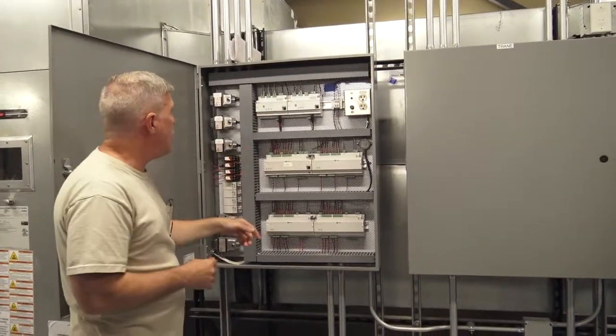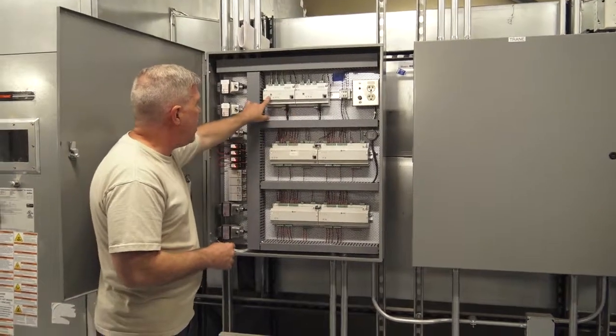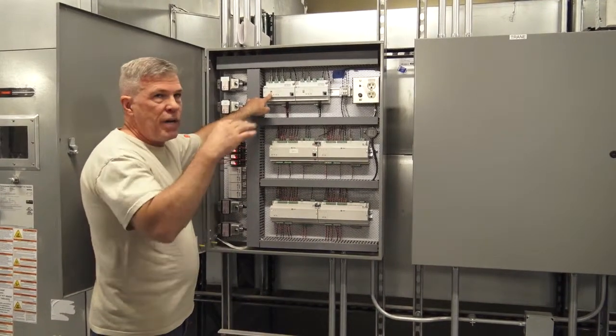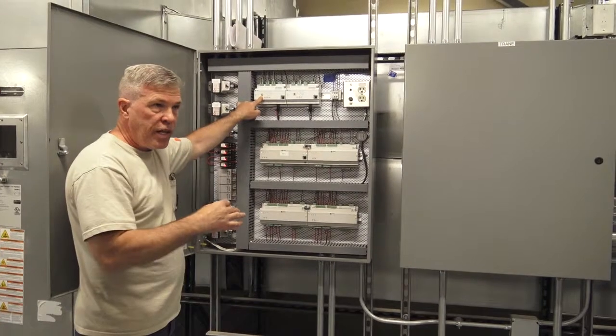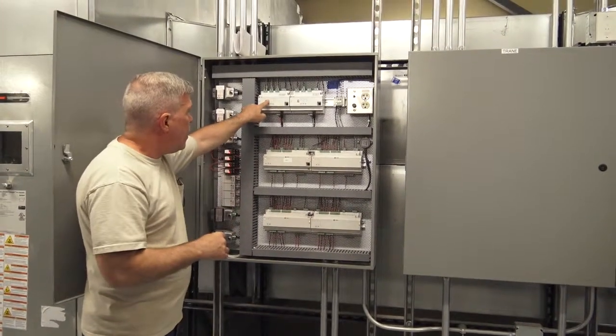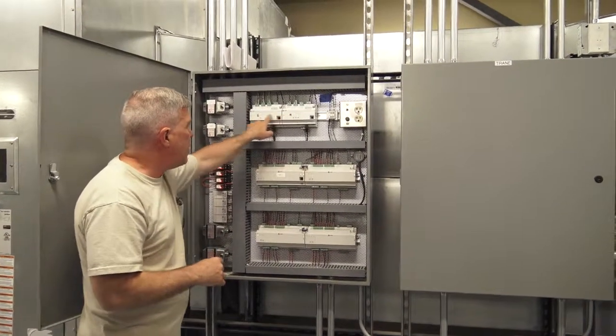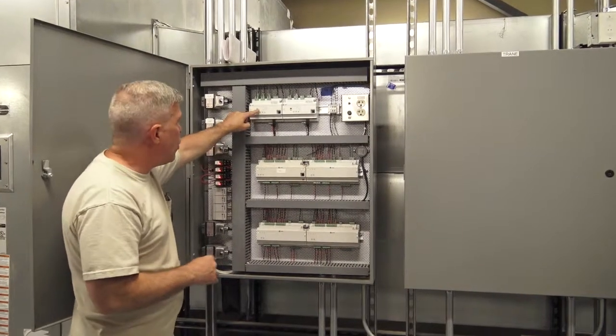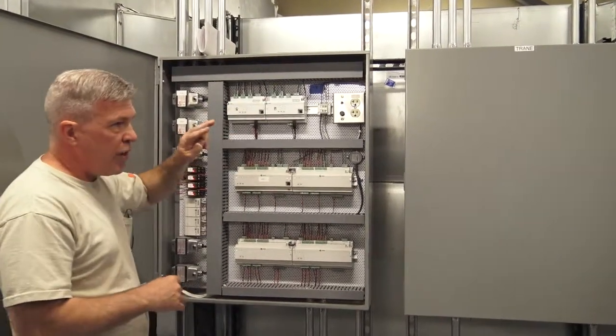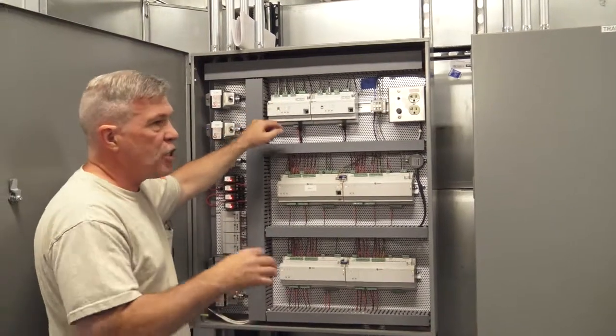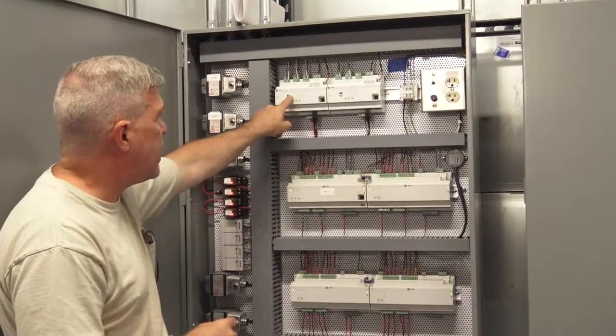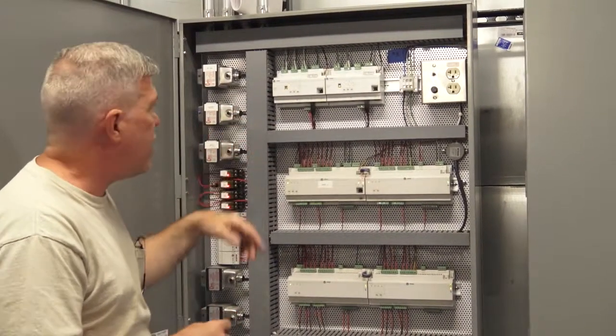That's a huge problem. What you're looking at here is the little dash going up and down tells you it's functioning correctly, you always want to see that. The next two sets of lights on each one of these are your comm links, you should always see them flickering. They flicker between green and yellow, but usually the green is so fast you don't see it, so you'll see the yellow flickering more than anything.